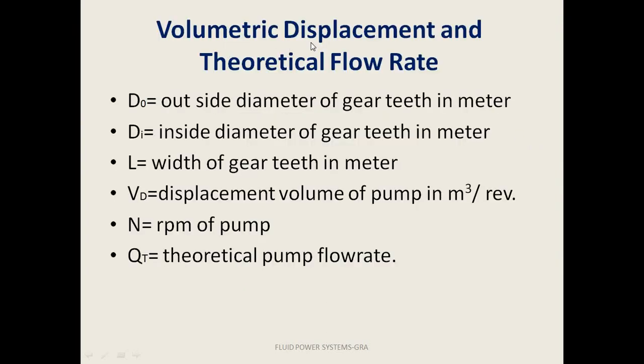Now, volumetric displacement and theoretical flow rate. We need to know the formulas for both these things because these are important. We are having numericals on this. If I consider d naught as the outside diameter of the gear teeth in meters, same thing as d i, which is the inside diameter, and L is the width of the gear teeth. If I take V D as displacement volume of pump in meter cube per revolution, that is how much discharge I am getting in one revolution, that is V D.